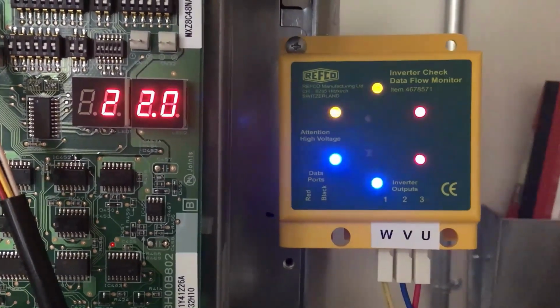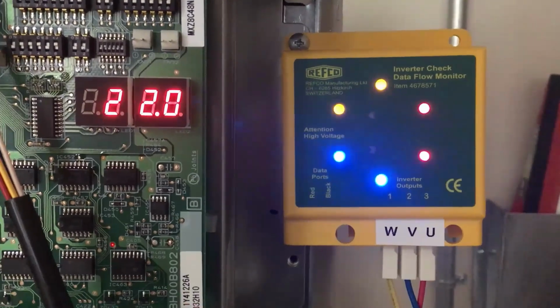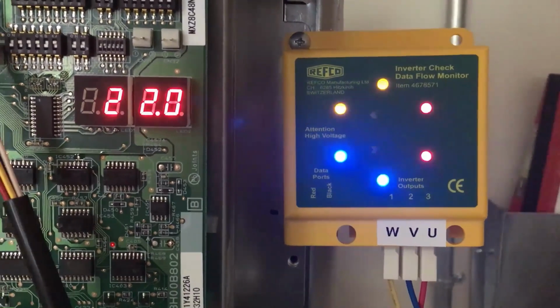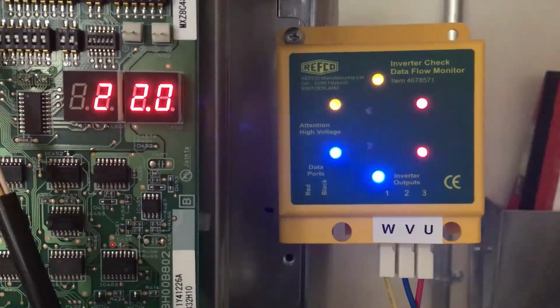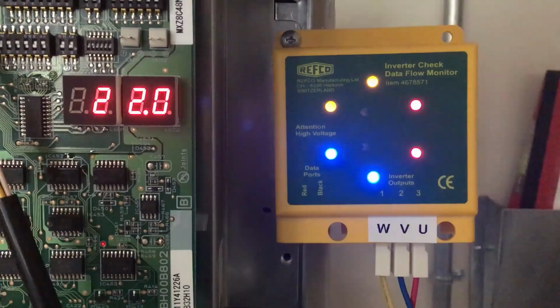Now this would be a balanced voltage check. All 6 of those lights are lit. All 6 IGBTs in the inverter are firing. And we are producing 3-phase power.